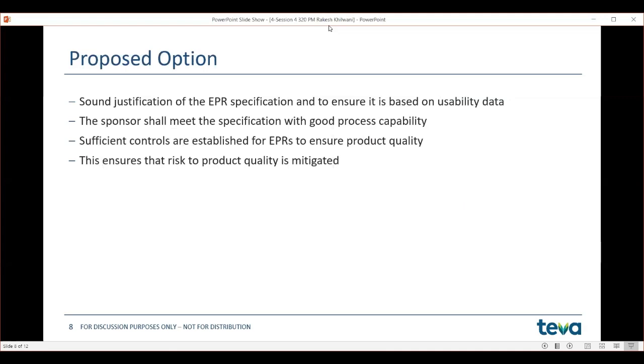So this is where I thought it'd be good to propose that one thing we could focus more on is how we are setting our specification, because that's where all the risks as well as the usability data would feed into. And as long as that is being set appropriately, meeting that specification with good confidence and reliability would ensure that we have built quality into our combination product. To go along with it, we should also demonstrate in our submission that there is good process capability and adequate controls in place to make sure that the submission batch and the production and commercial batches would have the same quality, so there has been no process shift. Essentially, we are trying to mitigate the risk to the product quality using this entire process.